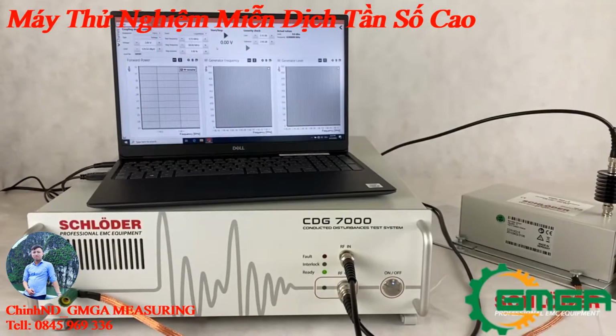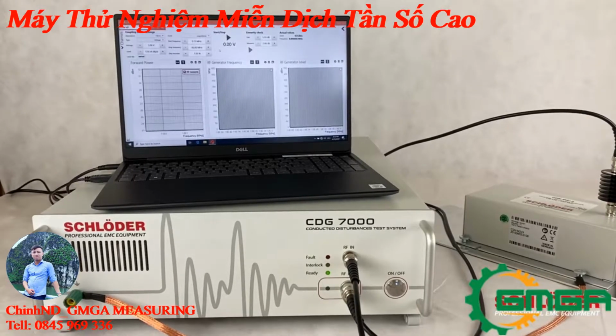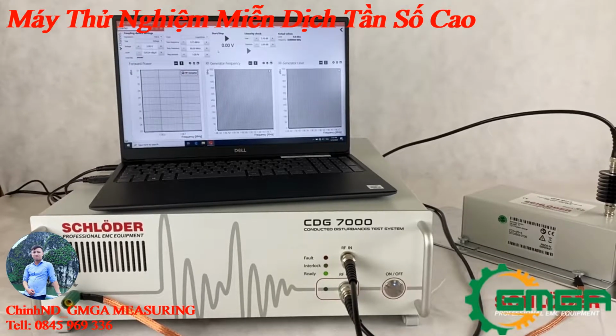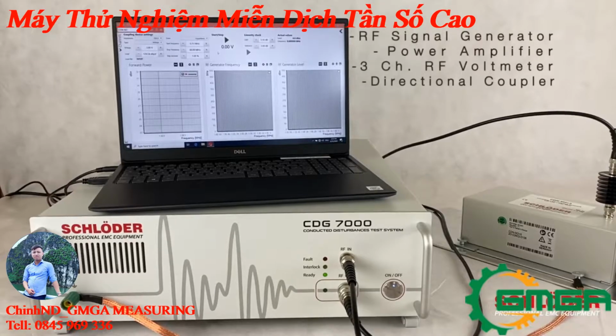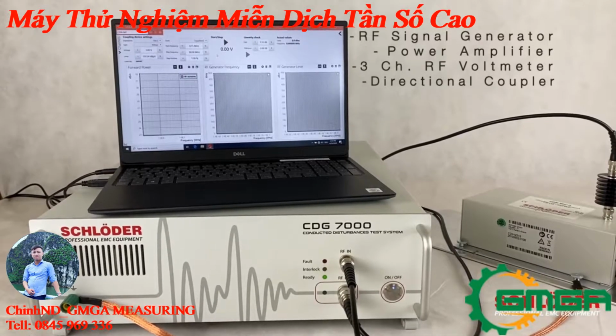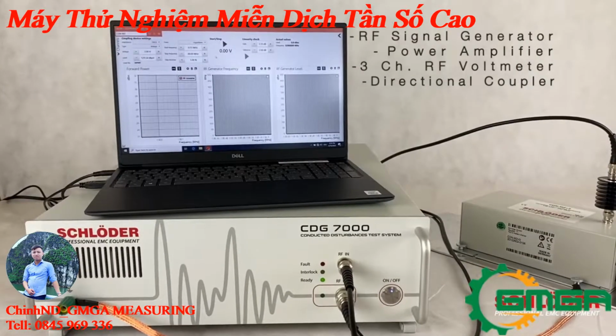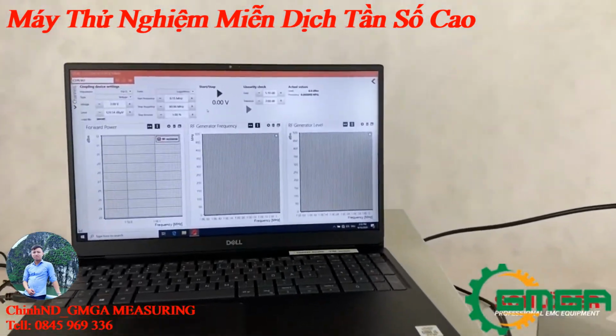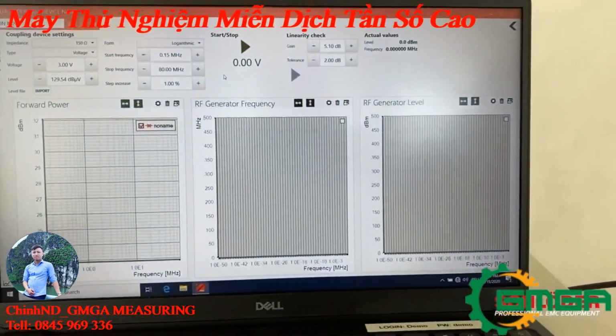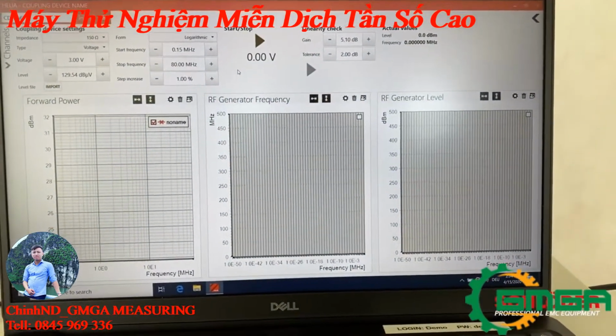Our CDG 7000 is one of the very few combined test systems on the market that contain an RF signal generator, an RF power amplifier, a 3-channel RF voltmeter, and a directional coupler. The device comes with our Helia software that can be used to fully control the whole system.